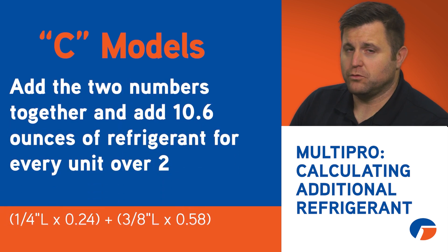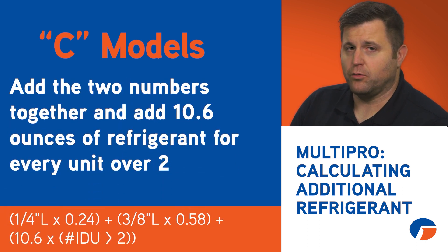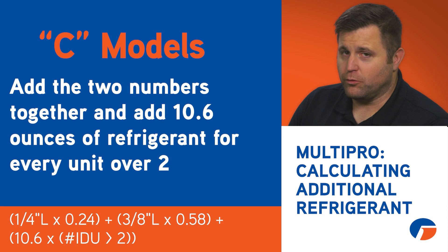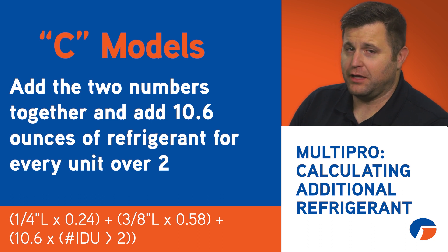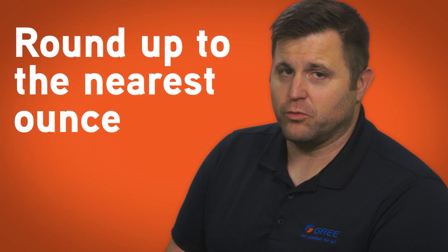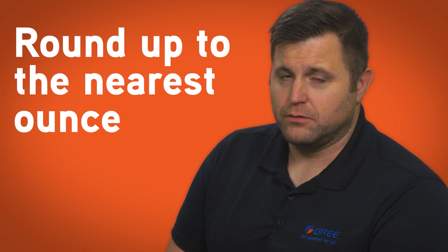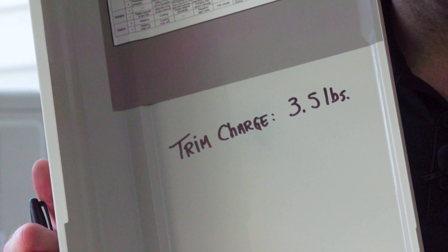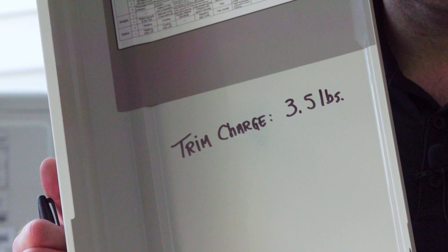You'll now add those two numbers together. Finally, you'll add 10.6 ounces for every unit over two — in other words, you'll add 10.6 ounces for the third, fourth, fifth, sixth, seventh, and eighth units. Then you'll round up to the nearest ounce. You'll write this down on the inside of the access panel on the outdoor unit for future reference.